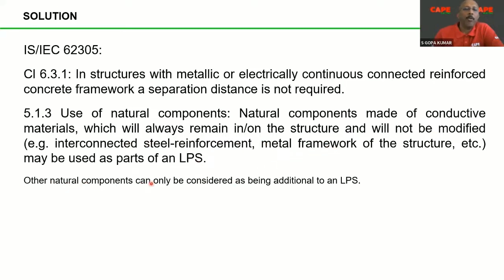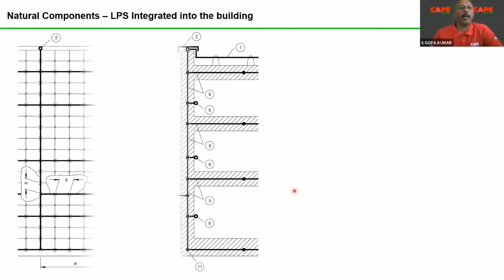Other natural components can only be considered as being additional to the LPS. What is the other natural component? For example, you have an aluminum facade. The frame of the aluminum facade has to be considered as an additional thing. It is not a steel reinforcement. It is not a complete metal framework for the structure. By metal framework for the structure, what the standard means is the column itself is steel, as in a PEB building. So your aluminum frame has to be considered as an additional thing, not as a down conductor.